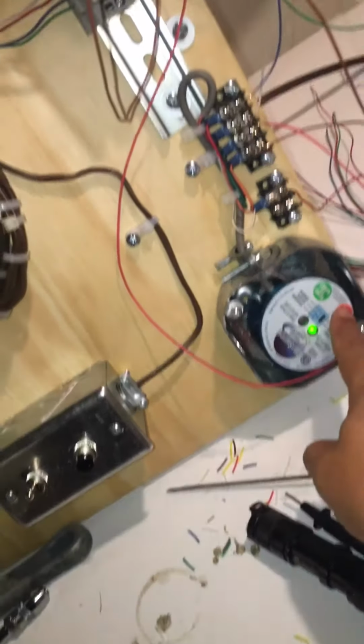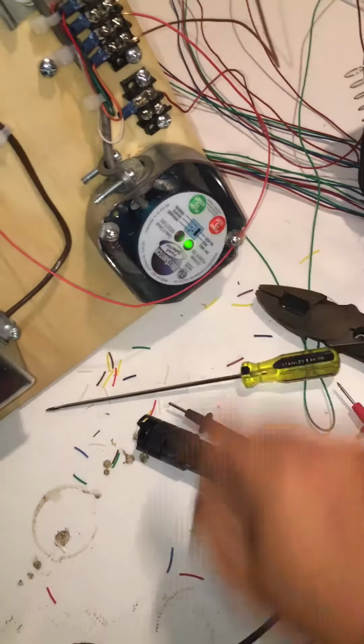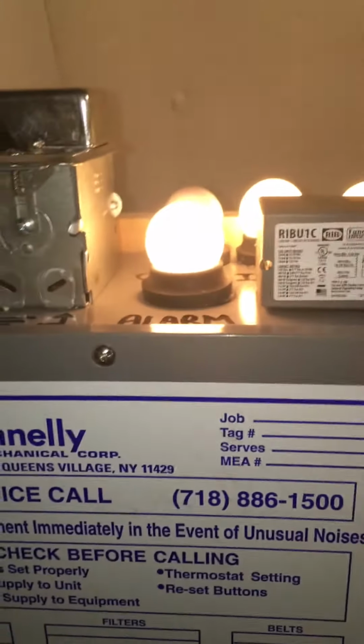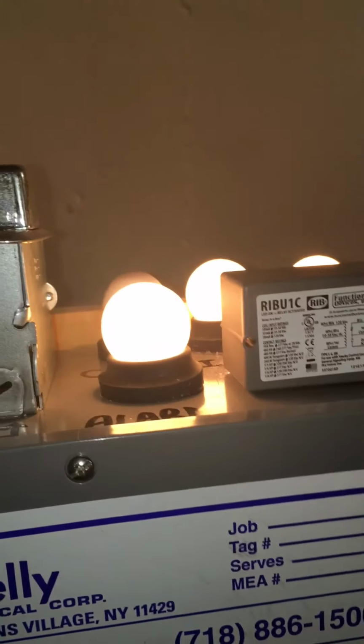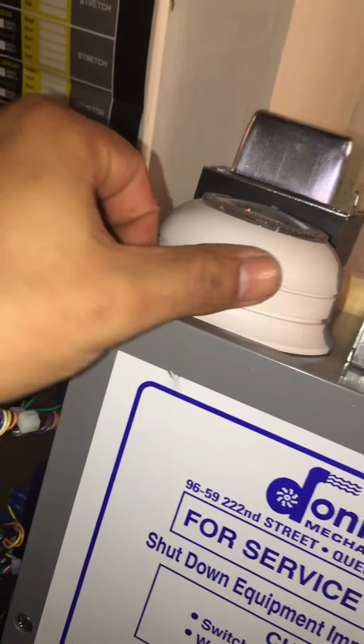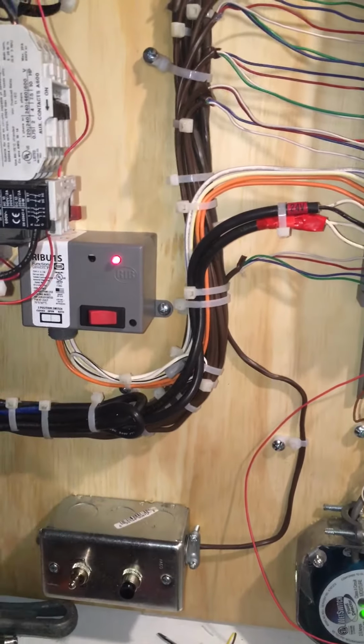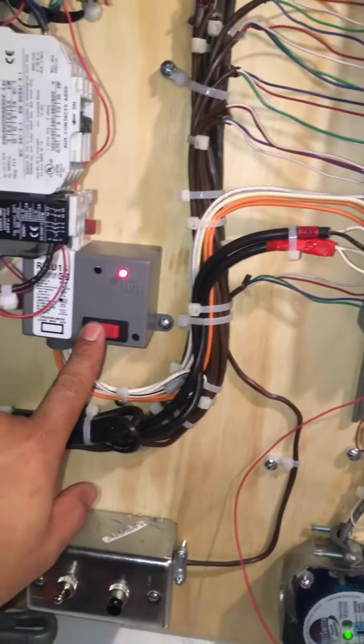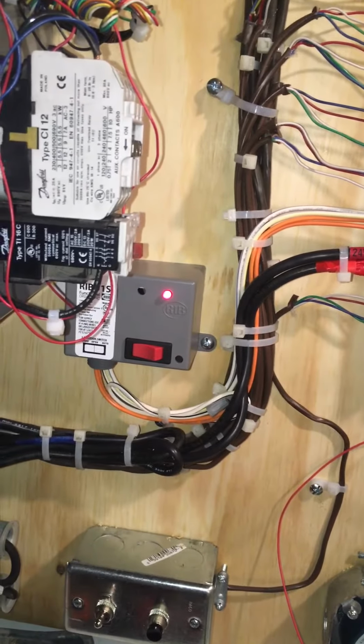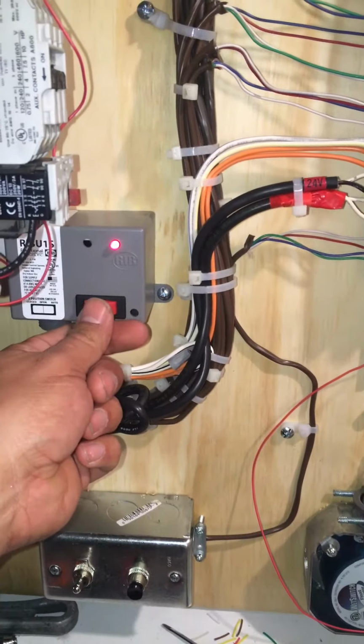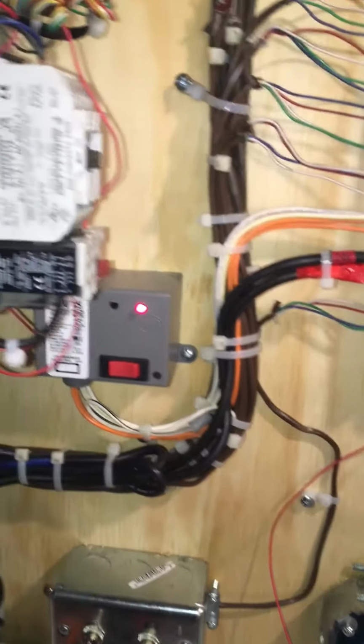Another feature is if we go into leak detection, we also eliminate the compressor and turn on the alarm. If we reset, we stay locked out. Same feature applies. Disengage cooling, turn back on cooling, and then as you can see, that light lights up. Even if I flip this to the hand, it won't turn on.